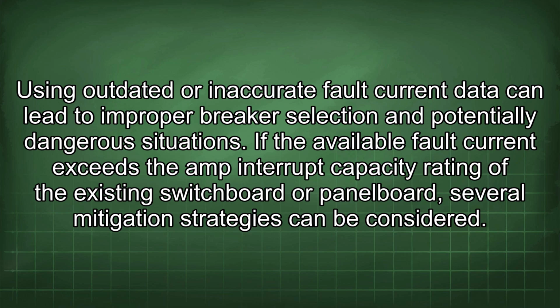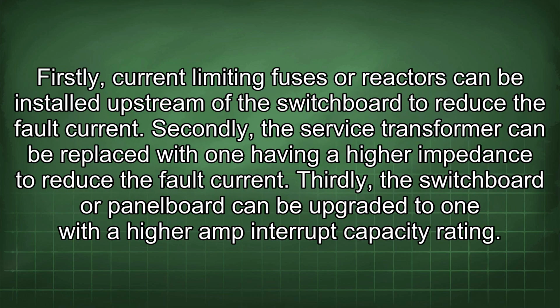If the available fault current exceeds the amp interrupt capacity rating of the existing switchboard or panelboard, several mitigation strategies can be considered. Firstly, current limiting fuses or reactors can be installed upstream of the switchboard to reduce the fault current. Secondly, the service transformer can be replaced with one having a higher impedance to reduce the fault current. Thirdly, the switchboard or panelboard can be upgraded to one with a higher amp interrupt capacity rating.